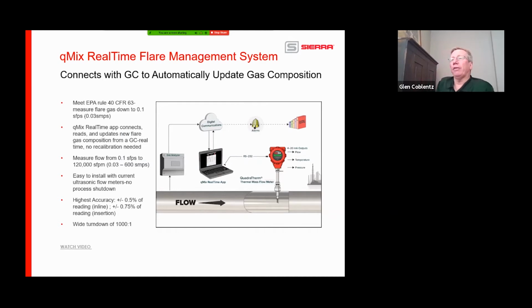All of these facilities have multipath ultrasonics, but what they found out is that to meet the regulations, the multipath ultrasonic is not going to work. Multipath ultrasonic can't measure the zero flow and it can't measure 100% hydrogen. Well, those are two things that the Q-Therm, Quadratherm can do really well. So we and the engineering team started working with some refineries on trying to come up with a solution, the kind of holy grail of a thermal mass flow meter: just sending it a new composition anytime you want and having the meter make that measurement. That day has now arrived.